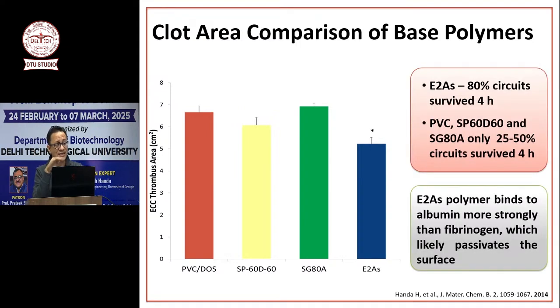Plus, 80% of the circuits survived in E2AS, whereas only 25 to 50% of circuits survived for 4 hours. I also told you yesterday, one of the things we do with this circuit is we measure the flow rate over a 4-hour period, right? So we measure flow rate, we count platelets every hour, we look at the clot formation in the end, and we also do aggregometry every hour to make sure that platelets are aggregating.